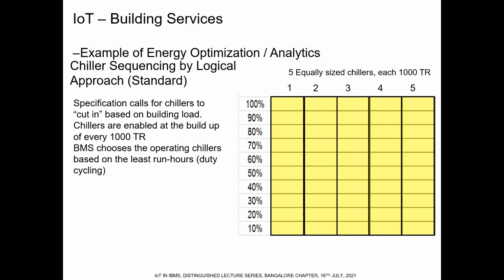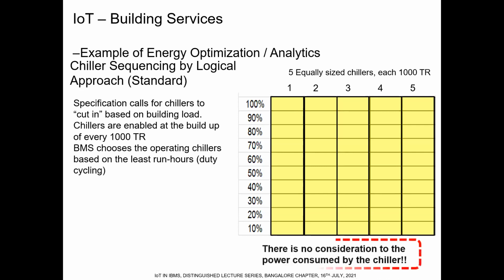In today's scenario, this is not rocket science. Every BMS vendor is expected to do this based on the common return water temperature or the amount of water that is coming, delta T, this, that, and the other. Those are the intricacies of the programming part. Now, what is not happening with this level of automation is any consideration of the power consumed by the chiller. This is clear automation by the number of chillers that are required as the load increases or decreases. There is no consideration of the power consumed by the chiller.